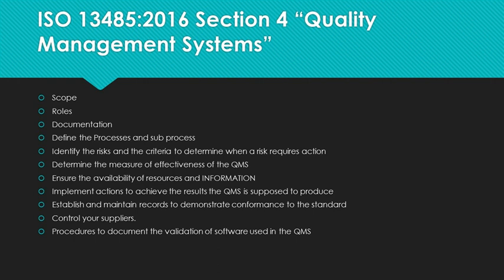Developing the QMS, you need to identify the risks and the criteria to determine when a risk requires action. When do you need to reduce the likelihood? When do you need to reduce the severity or increase the ability to detect a risk? The QMS needs to determine the measure of its own effectiveness — how do you know if it's working? Are there trends in key performance indicators? How do you know if you're getting better, worse, or staying the same? You need to ensure the availability of resources and information. You must implement actions to achieve the results the QMS is supposed to produce; if the QMS is not performing, you must act to fix it.